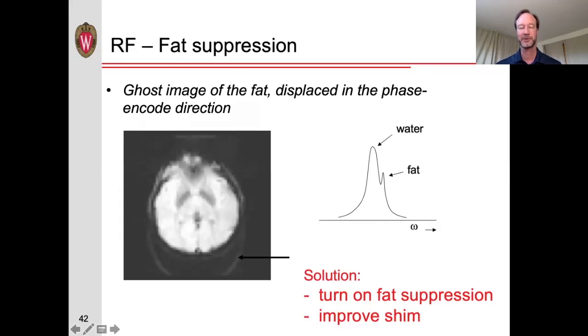Now, another solution to try to fix that would be, of course, turning on the fat suppression if it wasn't on to begin with. But also, this fat suppression loses its effectiveness if you have magnetic field non-uniformities. That is, if the fat peak isn't exactly where you expect it to be in terms of its resonant frequency, the fat suppression is not going to be as effective. And so improving the shim, that is, improving the uniformity of the magnetic field, can help with that.